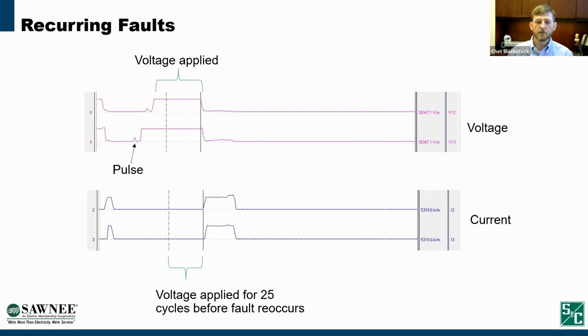That's fine if you're doing traditional reclosing, but if you're using pulse finding, that would cause your upstream devices to trip again, and it may cause them to go all the way to lockout. So in these situations, you have increased voltage sags, you have upline devices tripping sometimes all the way to lockout when these recurring faults occur. Next slide.